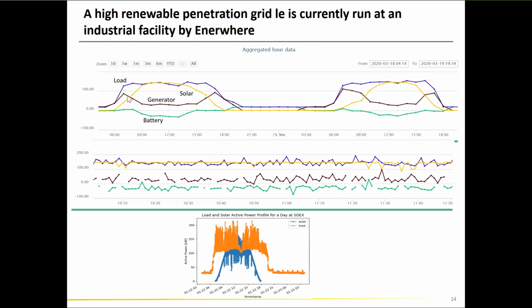Now the load fluctuates here by up to 100 kilowatts over one or two seconds. I will not be able to put in a lot of solar here unless I have something to stabilize that grid. Most microgrids globally cannot penetrate as much solar as we are doing here, because one major reason is you don't have anything to stabilize that grid. If I have solar there and you have a largely fluctuating load, my source of generation cannot take in that power and cannot handle that reverse flow of power.